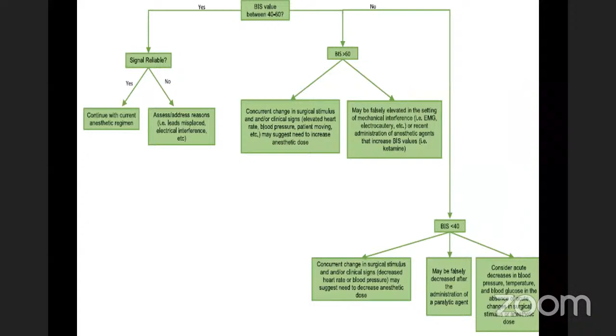First of all, we have to decide whether the BIS reading is between 40 to 60. If yes, then is the signal reliable? Yes, the signal is reliable. We can continue with the current regimen. If the signal is not reliable, we have to address the reasons, whether the lead is misplaced or there is electrical interference from other interfering agents like cautery.